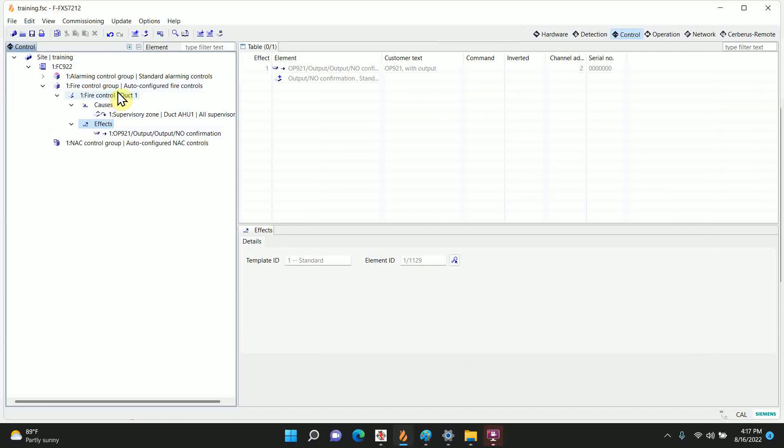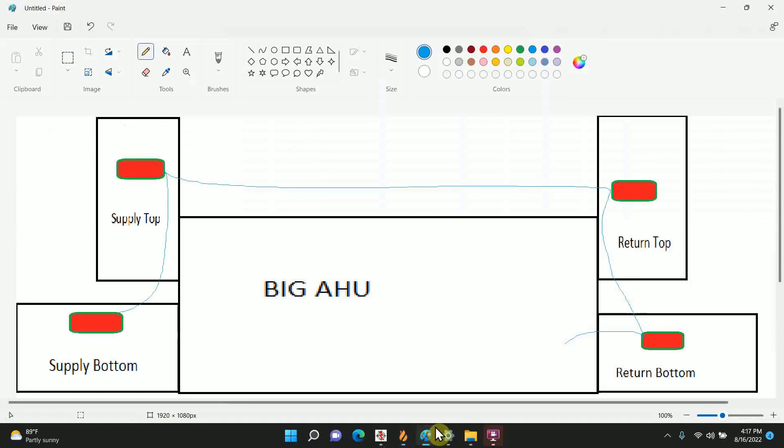Now that duct detector is now a standalone duct detector. If it goes into a supervisory alarm, it will trigger its relay. But if we want to use that example again here where any one of these four are going to trigger this bottom, we're going to go back to it and we're going to add the others.